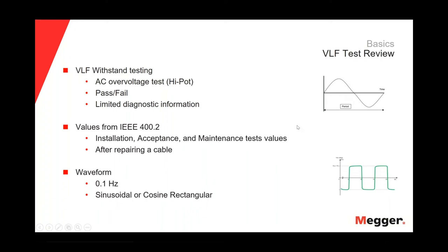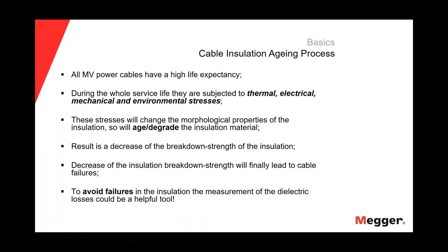Today, in the present, we could say that all medium voltage power cables have a high life expectancy, okay? But during their service life, they are subject to thermal, electrical, mechanical, and environmental stresses. And these stresses will change the morphological properties of the insulation. In other words, they will age or degrade the insulation material of the cable. So this will result in a decrease of the breakdown strength of the insulation, and the decrease of the insulation breakdown strength will finally lead to cable failures. And of course, to avoid failures in the insulation, the measurement of the dielectric losses could be a helpful tool.